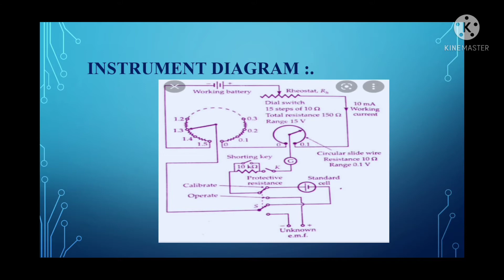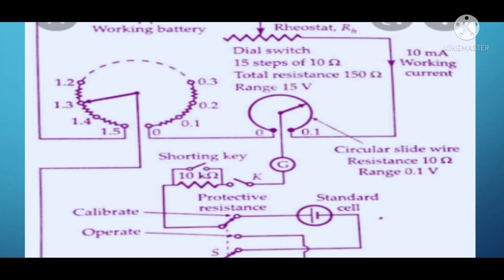Let's discuss the constructional features of this laboratory type potentiometer. This is the structure of a Crompton potentiometer, where we have this dial switch arrangement and the circular slide wire. By means of this circular slide wire arrangement, we can measure precisely up to 3 decimal points. The increased length of slide wire is replaced by these two arrangements. As usual, the potentiometer measures unknown voltage values. This instrument also measures the unknown voltage value, but its operation differs. Only the medium of movement of the sliding contact differs here, whereas all other things remain the same.